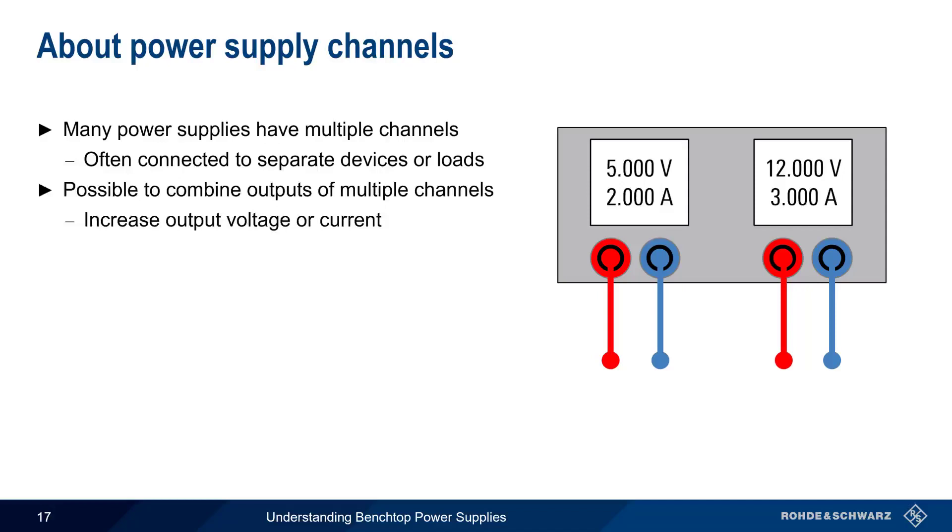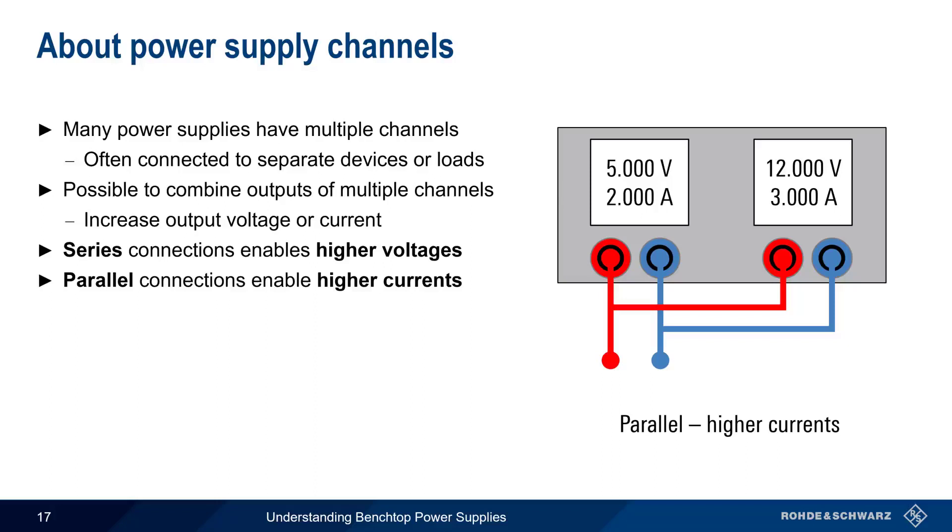There are two ways power supply channels can be combined. If the channels are connected in series, this enables higher voltages. On the other hand, if the channels are connected in parallel, this enables higher currents. These connections are typically made externally, although in some cases, the connections may be made within the supply itself.